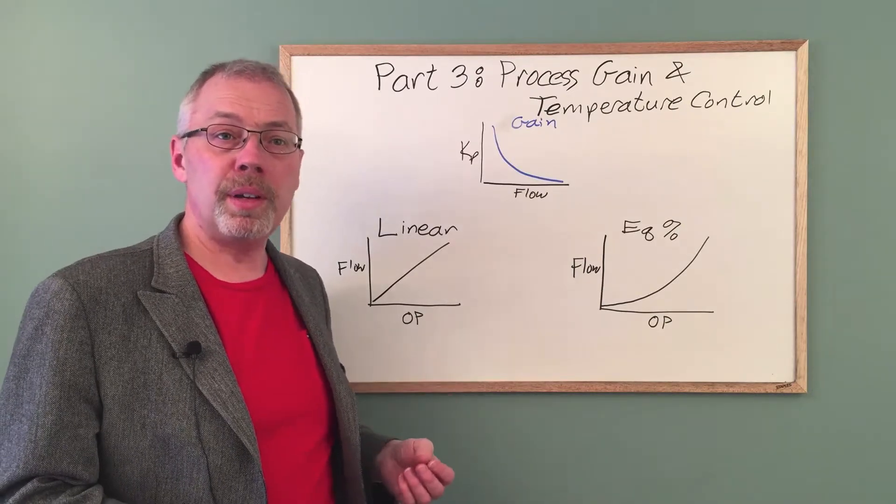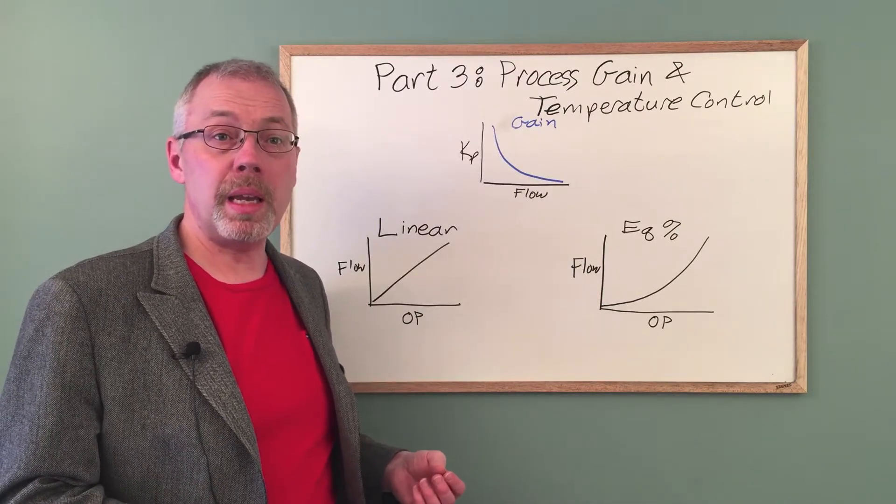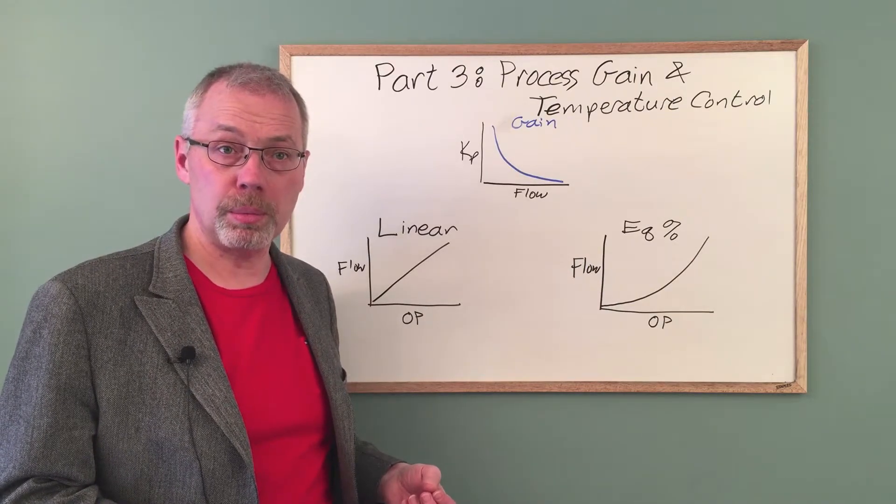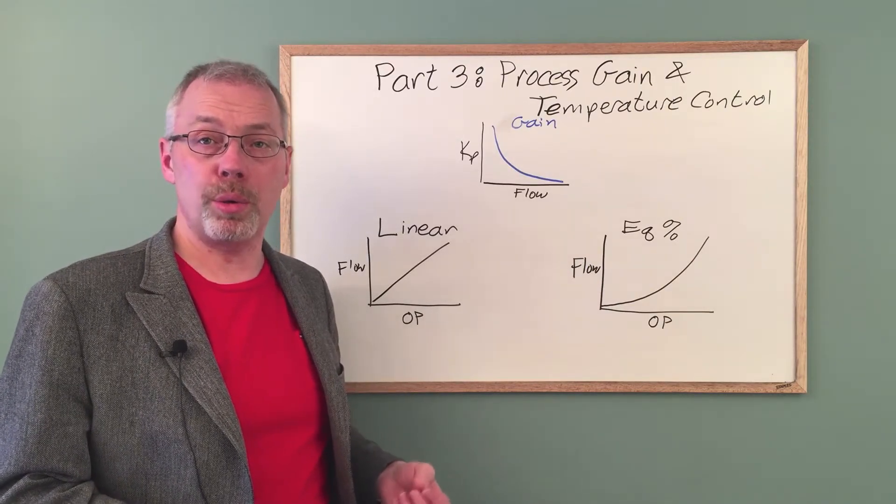If a linear valve is used, the process gain will be high at small valve openings and low at large valve openings. The process gain is not uniform.